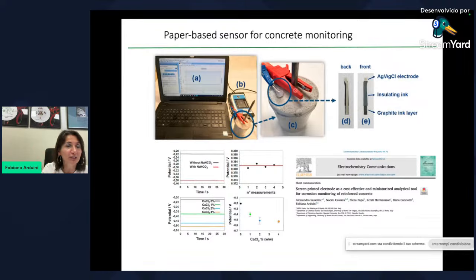In the classical method, the method used now, they use a wet sponge and a bulk copper sulfate electrode as the reference electrode. In this work, we demonstrate that it's possible to miniaturize the system because we use, of course, the bar, and we use the printed electrode, in this case on polyester, and to close the electrochemical cell, we use hydrogel loaded with KCl. We demonstrate that with a really cost-effective system we can evaluate the corrosion level of the concrete structure because the potential changes.